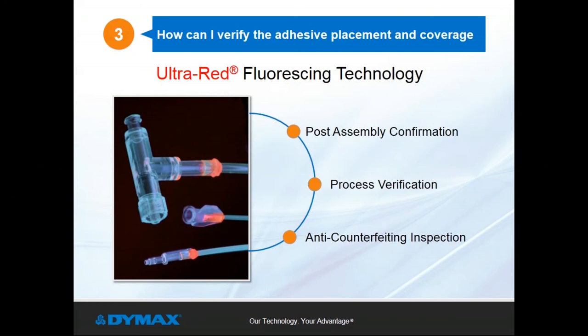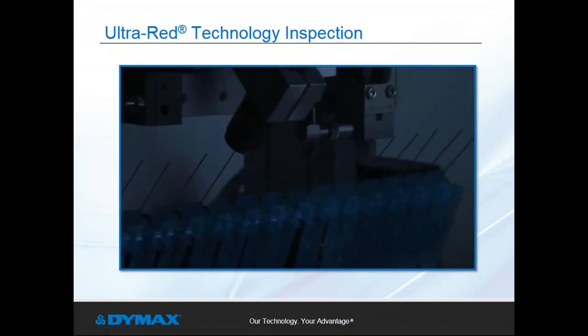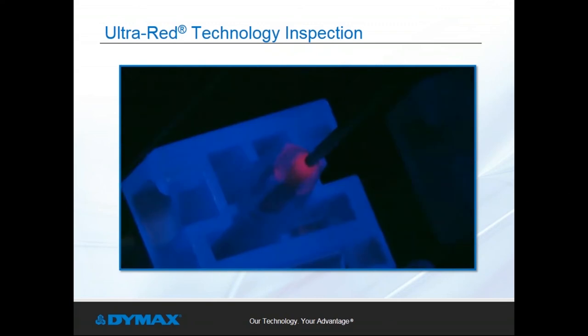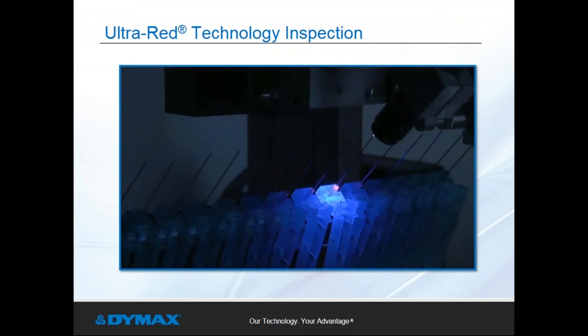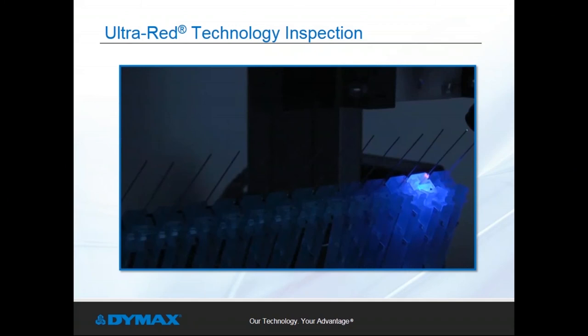DYMAX developed ultra-red fluorescent technology to provide vibrant contrast against the natural blue-fluorescing properties of many plastics. This bright red color is triggered by exposure to low-intensity 365nm blacklight. The contrast is perfect for both process verification and anti-counterfeiting. In a video example, a batch of needles slides through a vision system inspection — the ultra-red technology is activated almost instantly after a flash of low-intensity 365nm blacklight, and the contrast is easily detected by the vision systems. This technology is equally valuable for inspection before cure, especially on expensive device assemblies where rework may not be an option.